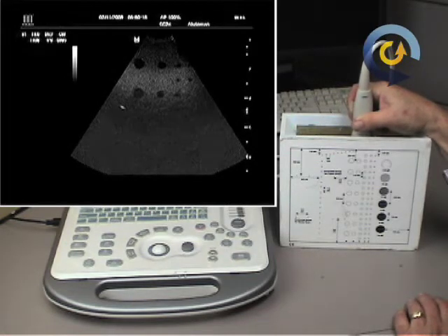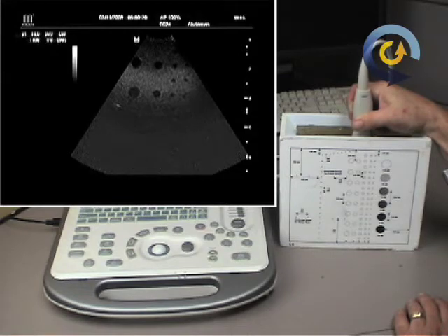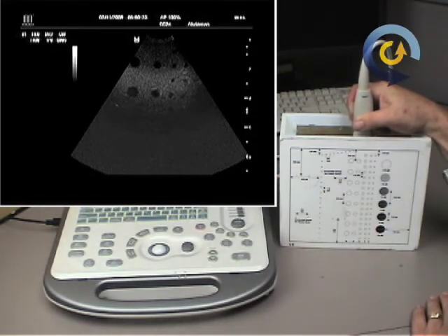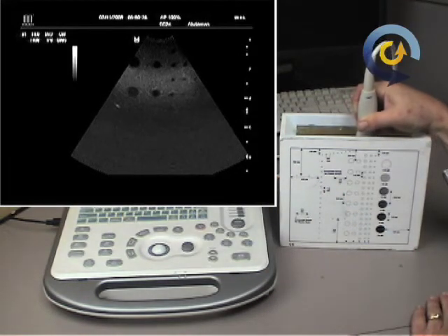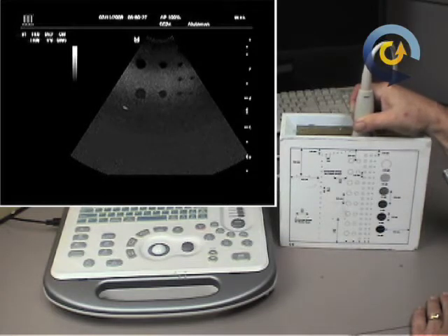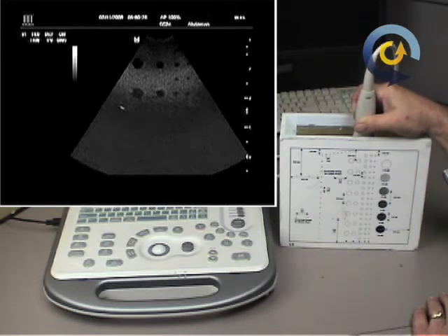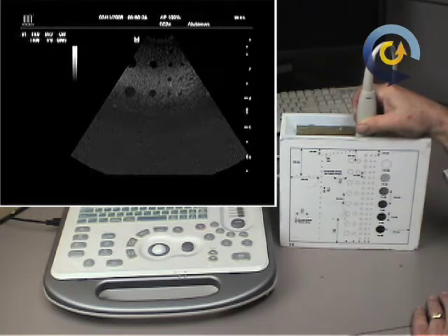Those are the most typical uses of an ultrasound phantom, and an ultrasound 2D grayscale phantom like this one, a tissue mimicking phantom, is by far the most common. I told you there were other phantoms, the ones I mentioned before, such as the breast, the prostate, and the head and neck. Those are just similar phantoms with a little different physical structure so that you can put a transducer that would be used for that.